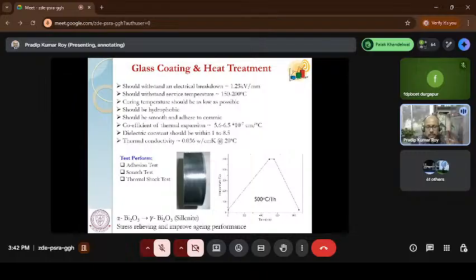So you need certain properties for this insulation. For example, the breakdown voltage should be around 1.25 kilovolt per mm. It can withstand more than 200 degrees Celsius. It should be completely hydrophobic. It should adhere very well to the ceramic block. It should have very low thermal expansion. It has a dielectric constant around 8.5, and thermal conductivity should be as low as possible, because I said it's a purely insulator material. There should not be any leakage, defects or flaws around the block. Otherwise, there is a chance of flashover around the side of the block when the surge comes.